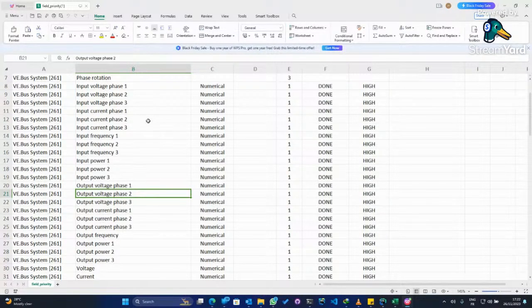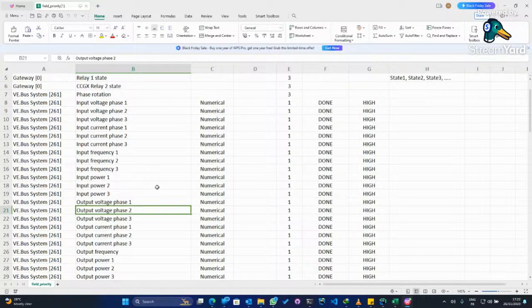We all know that power is a function of current and voltage. One thing we have discovered about this data set is that once you use the current and voltage at any moment, the product of those will always give you the power consumption, independent of the power source on which the site is operating. If the site is operating on battery or on grid, it doesn't change anything about the power it has to be using.